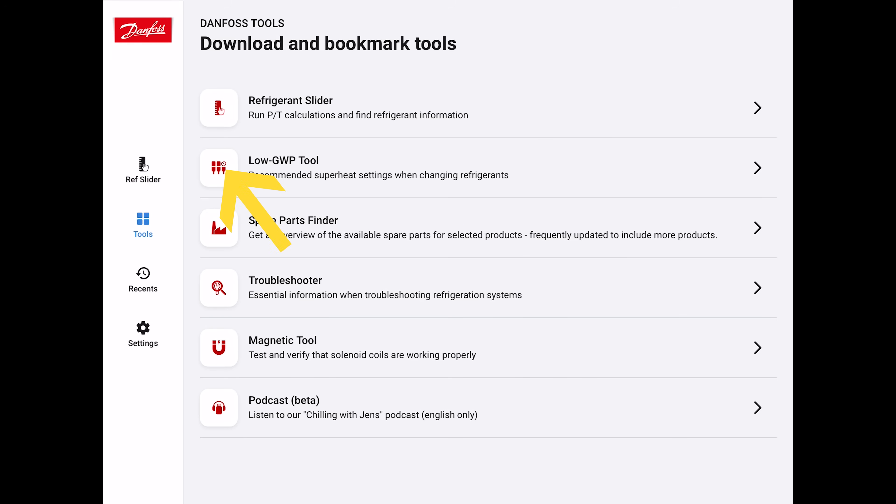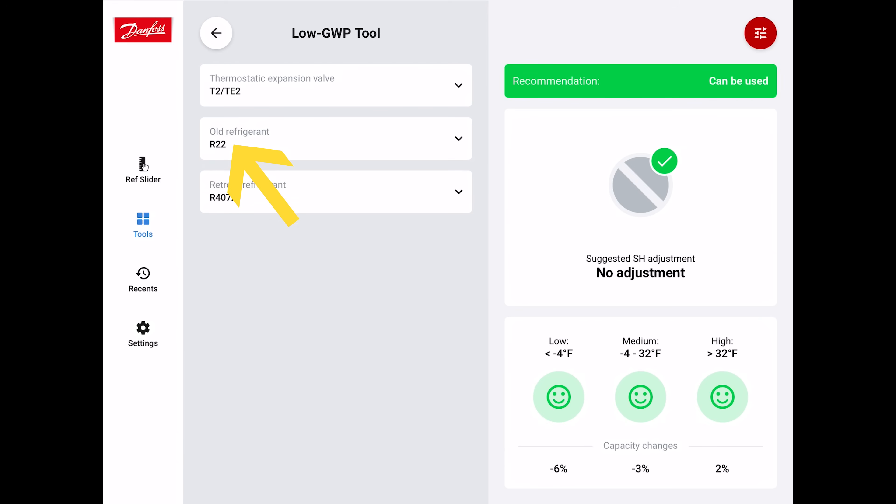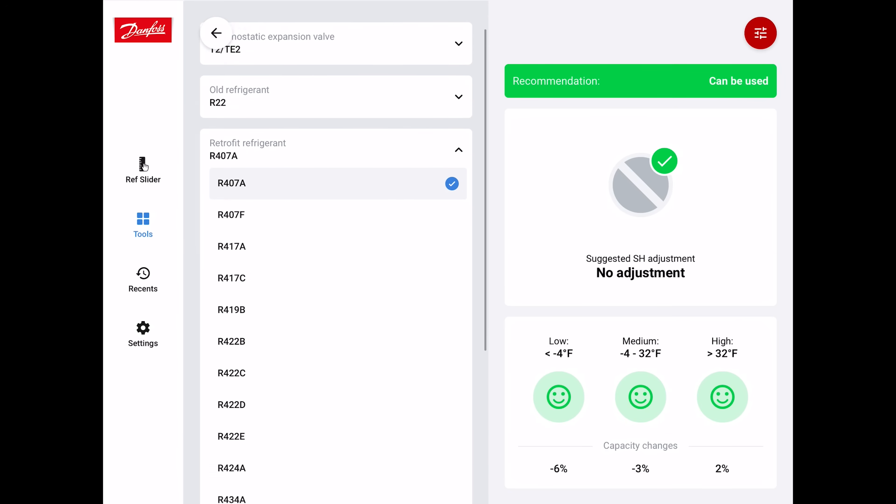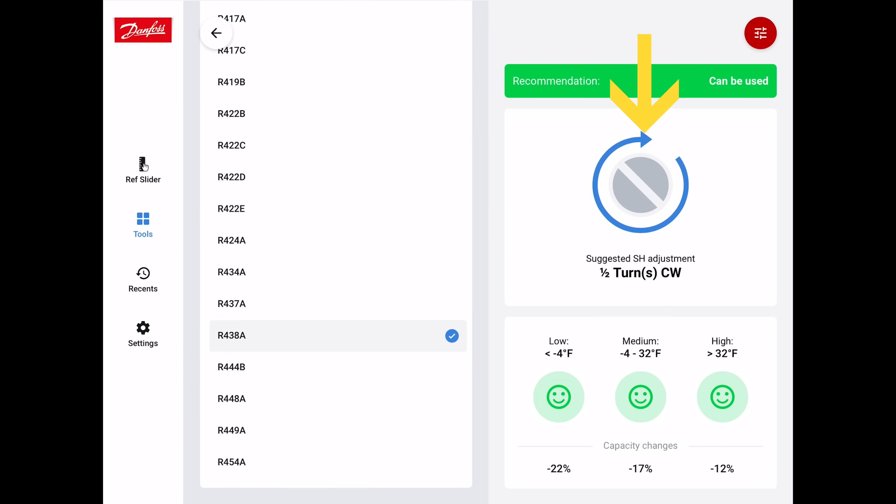Now let's go to the low GWP tool. If we have a unit where the old refrigerant was R22 and it had an R22 TXV, this low GWP tool is going to recommend the adjustment on the thermostatic expansion valve on the spring on the bottom there. If the retrofit refrigerant is R438A, it's suggesting that you do a half turn clockwise to adjust the superheat.